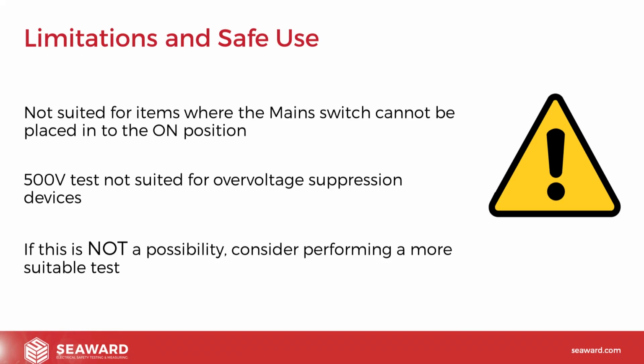And it's also not recommended in the event that you cannot engage a mains voltage switch. So, for example, a contact switch on a concrete mixer, if you've got that sort of environment, then a dead test, i.e. a flash or insulation resistance, may not be suitable at all. In such cases, it's probably more suitable to perform the other tests that we're going to talk about today, the mains powered tests, because they're done while the unit is operational and powered on. So we'll discuss these as we move on now.